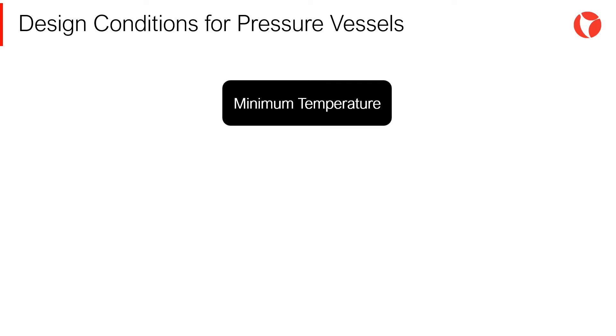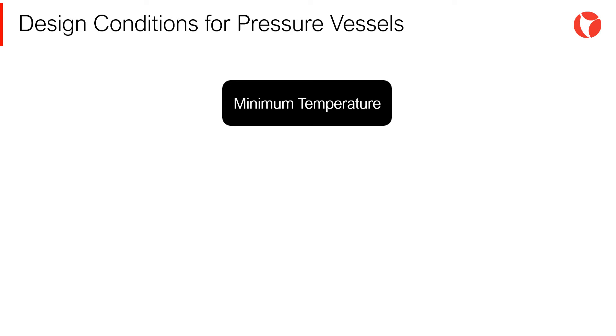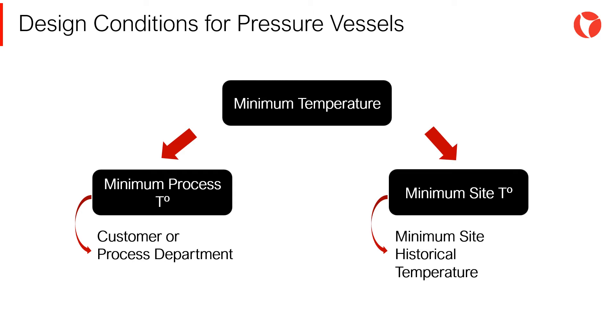The minimum temperature at which the pressure vessel will operate is the minimum value of: first, the minimum temperature provided by the customer or the process department; and second, the minimum temperature of the site, which is determined based on historical data.